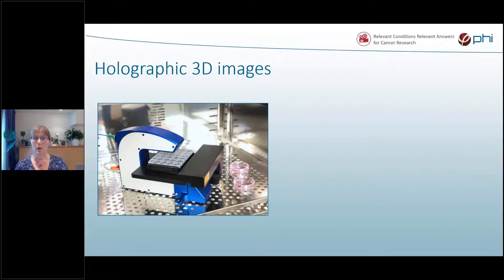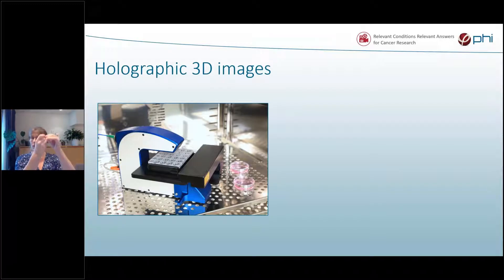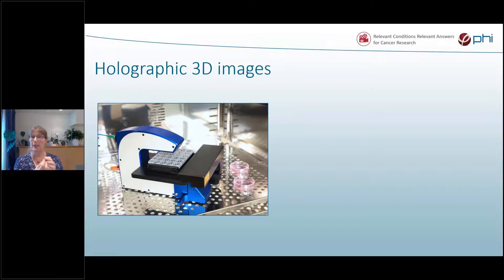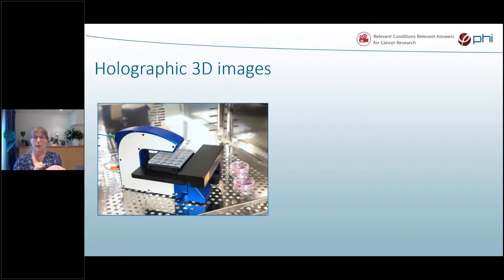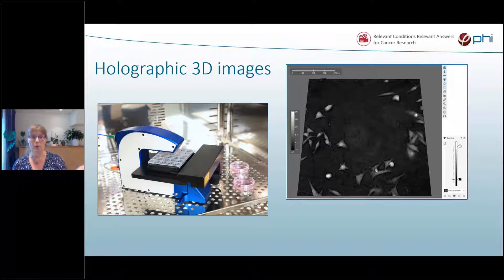How does the HoloMonitor work? We use digital holographic imaging — you can get 3D images out of this technique. Very low intensity light passes through the cells; when the light passes through a cell, it is delayed. If the cell is thicker or more dense, the light is delayed more; at thinner edges, the delay is less. That is what we measure — the delay of the light. The computer then calculates, for each pixel in the image, how thick the cell is and makes a cell drawing. The thicker cells appear whiter in the image.